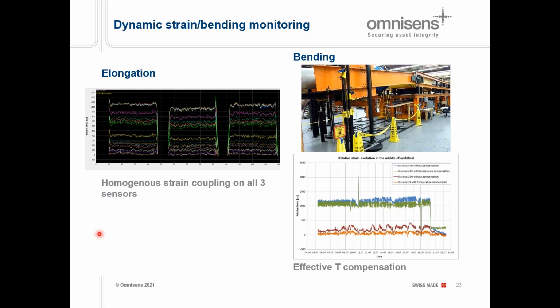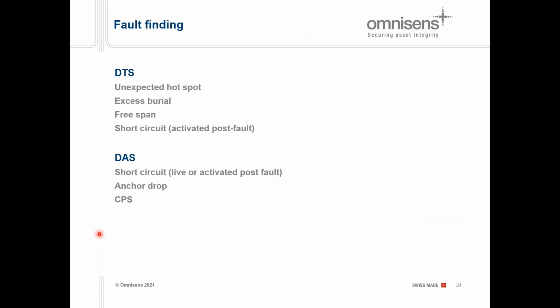We can do fault finding with these technologies. With DTS, we have access to unexpected hotspots, excess burial, free span, and short circuit by activating the cable post-fault. With DAS, we can detect short circuit at the time of the fault and also by post-activation. We also have access to anchor drop and the quality of the cable protection system. I'll come back to these later on.